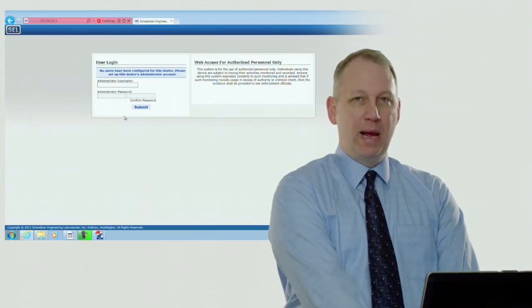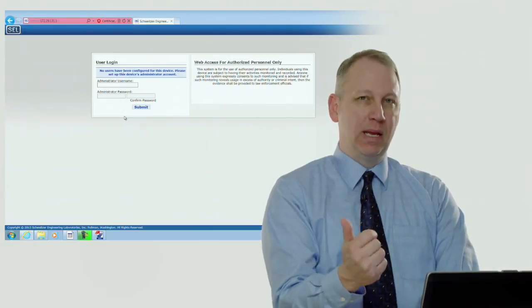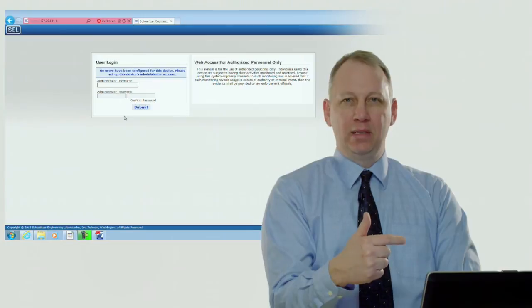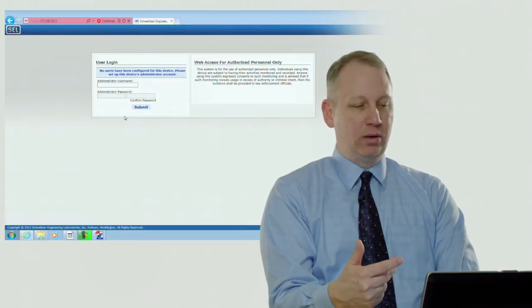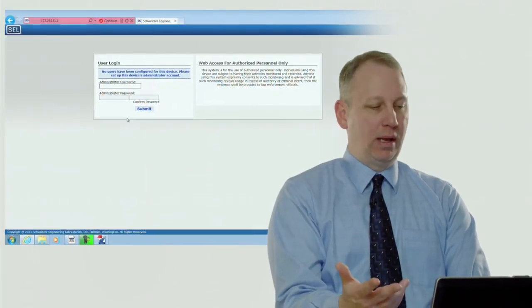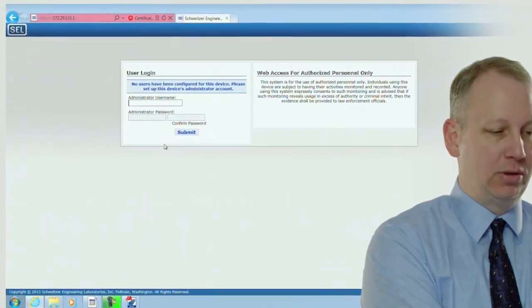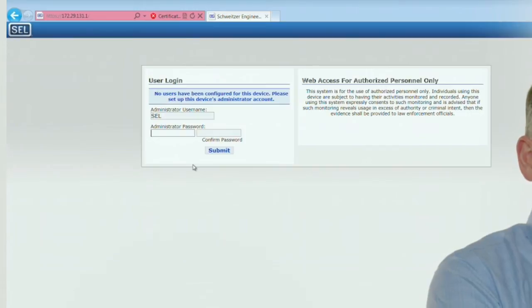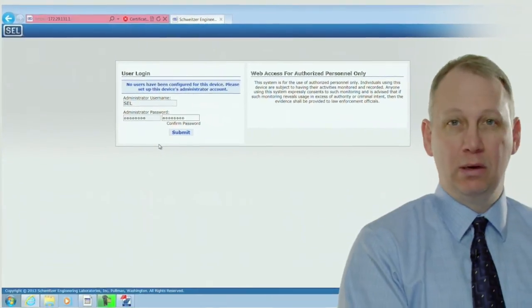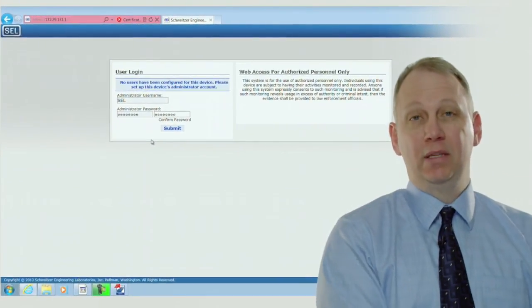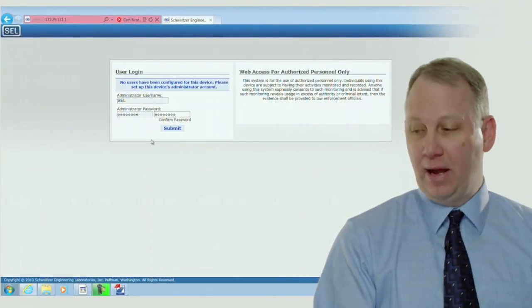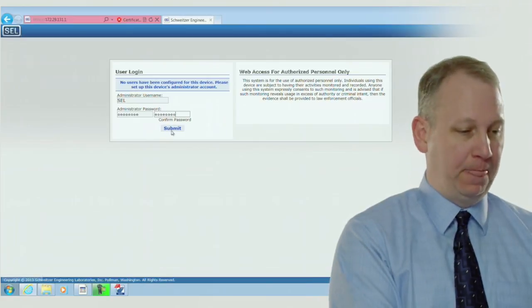The initial password has to be a complex password, so that means it has to be at least eight characters, has to have uppercase and lowercase characters as well as a number or two and also a special character. So what I'm going to do is make this SEL and any password that you want. Just make sure to write it down and don't forget it, because if you forget it there is no backdoor so you'll have to take the unit apart and reset it.